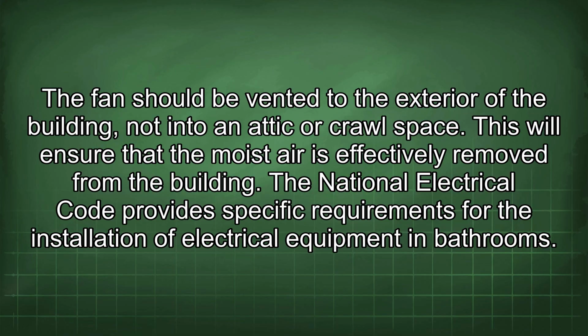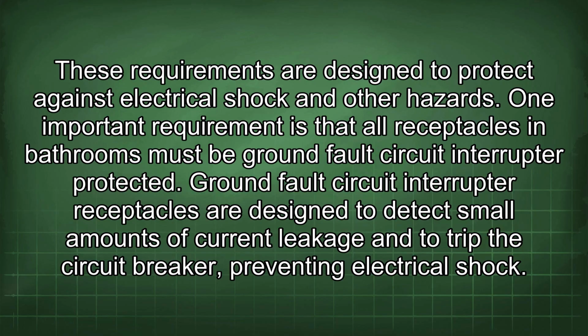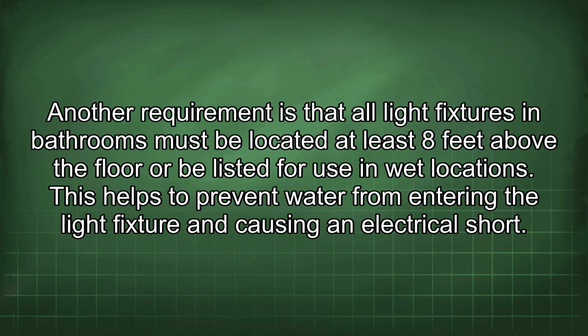The National Electrical Code provides specific requirements for the installation of electrical equipment in bathrooms. These requirements are designed to protect against electrical shock and other hazards. One important requirement is that all receptacles in bathrooms must be ground fault circuit interrupter protected. Ground fault circuit interrupter receptacles are designed to detect small amounts of current leakage and to trip the circuit breaker, preventing electrical shock. Another requirement is that all light fixtures in bathrooms must be located at least 8 feet above the floor or be listed for use in wet locations. This helps to prevent water from entering the light fixture and causing an electrical short.